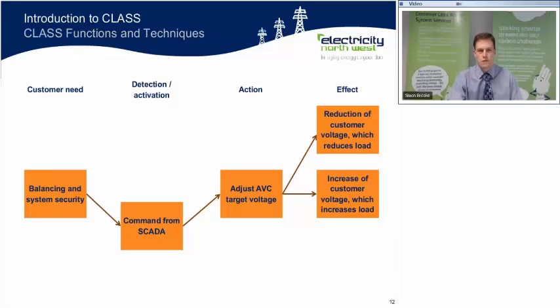So the first function we're looking at is balancing system security. That's the need for this function. And this is a function which is activated using a command from SCADA. Upon receipt of the activation signal, the equipment in the substation will adjust the AVC target voltage, and then the AVC relays will adjust the tap changers on the transformers, with the effect that the voltage will be raised or lowered, which will cause an increase or reduction in load.